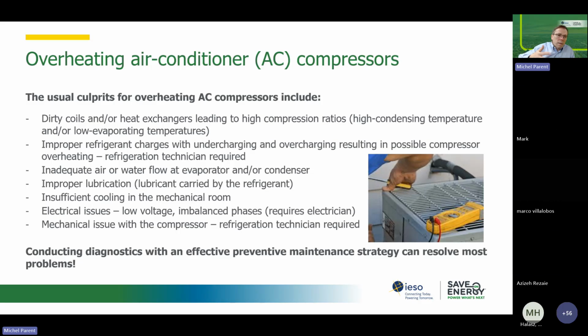If it's a water-based system, obviously the water flow is the same as airflow. So improper flow can sometimes, but rarely, be an electrical issue, just like we talked about with the motors, where either your voltage is too low or you've got imbalanced phases. It is not the most common reason, but if you see systematic issues with your compressors, your motors are all burning out, and you check your voltage and for some odd reason it's lower. There's always that rule: voltage low, amps high, and the amps are the ones that create heat. So you want your voltage to be close to the nominal voltage so that your amps go down. There's always this relationship between amps and voltage.